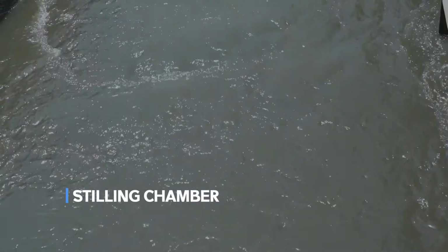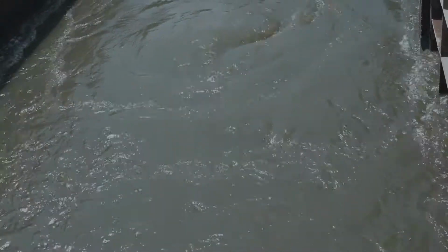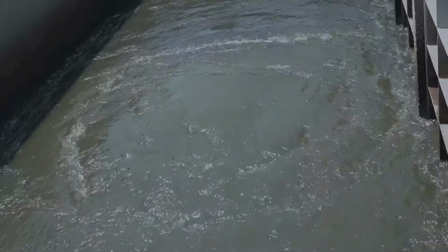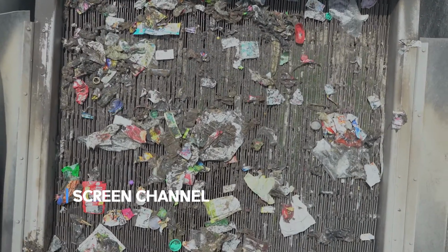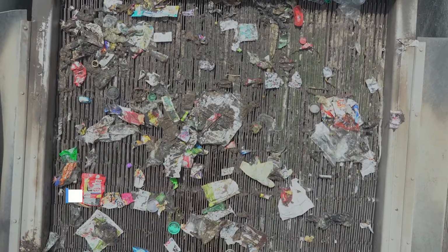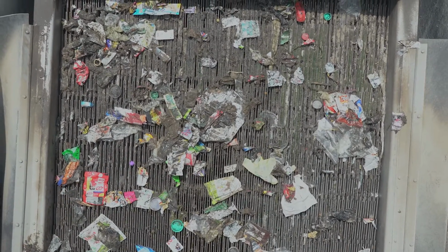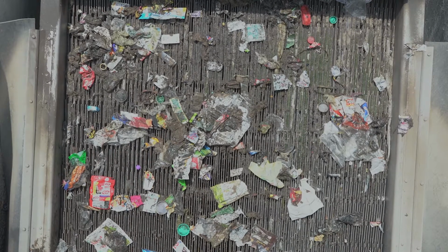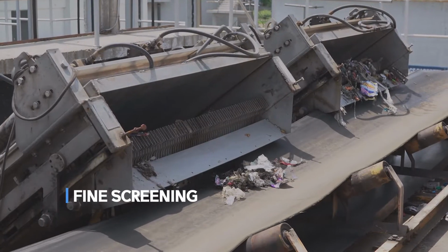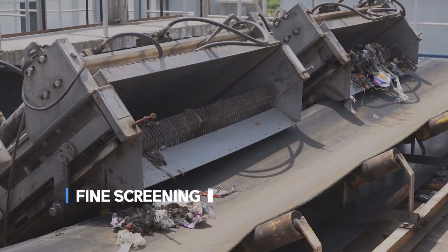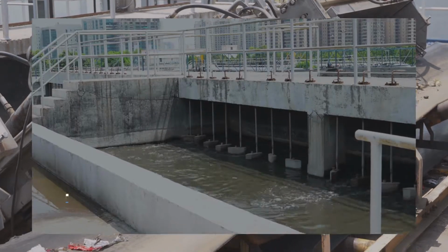A stilling chamber is provided at a higher ground level to receive raw sewage from the pumping station. Its purpose is to dampen the velocity of sewage. After the stilling chamber, sewage enters the screen channel with 5 parallel channels, with 3 being used for mechanical screen while 2 are for manual fine screen. Mechanical fine screen is controlled by a level transmitter provided in the screen channel.